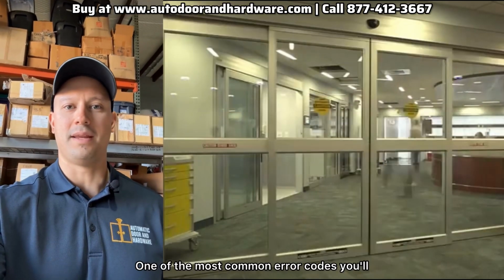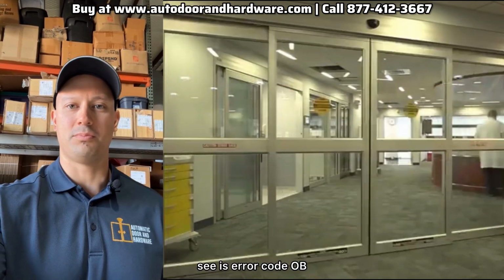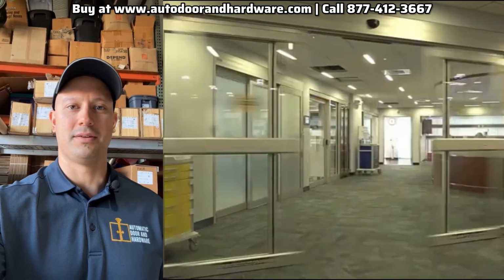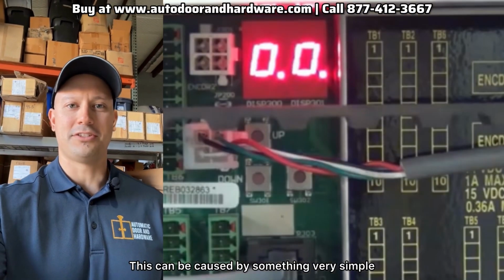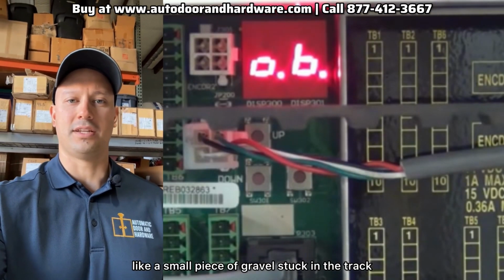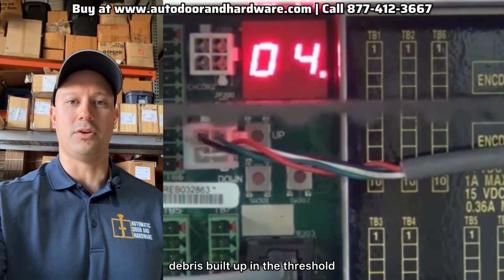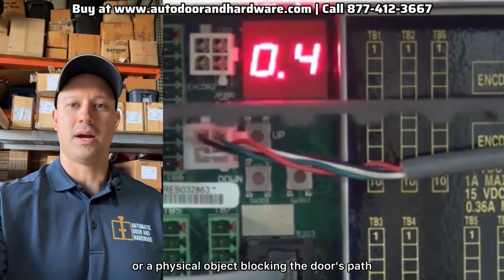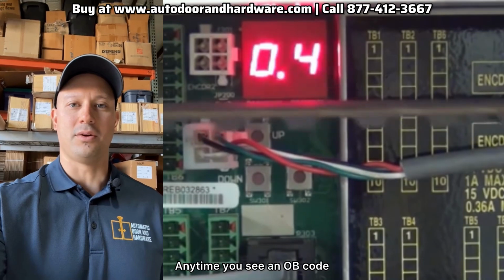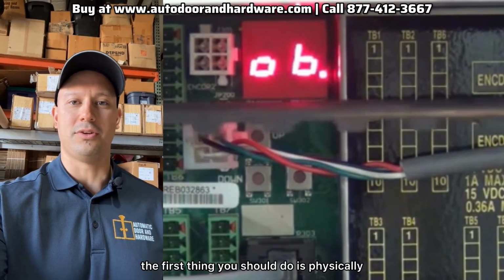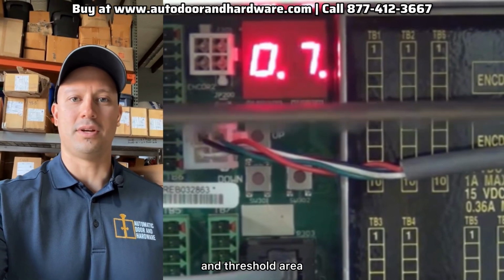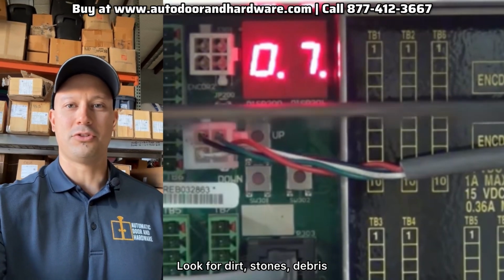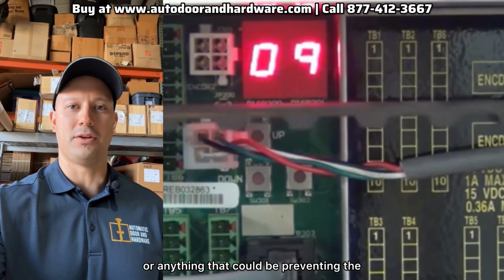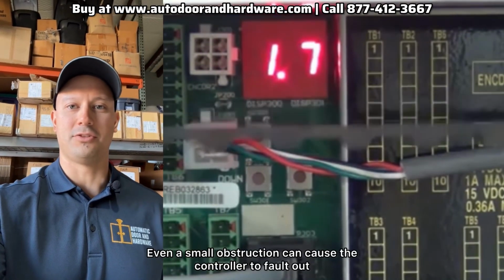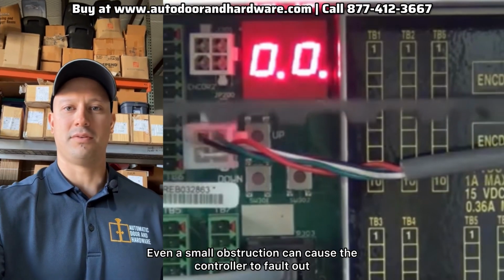One of the most common error codes you'll see is error code OB, which indicates an obstruction. This can be caused by something very simple, like a small piece of gravel stuck in the track, debris built up in the threshold, or a physical object blocking the door's path. Anytime you see an OB code, the first thing you should do is physically inspect the track and threshold area. Look for dirt, stones, debris, or anything that could be preventing the door from moving smoothly. Even a small obstruction can cause the controller to fault out.